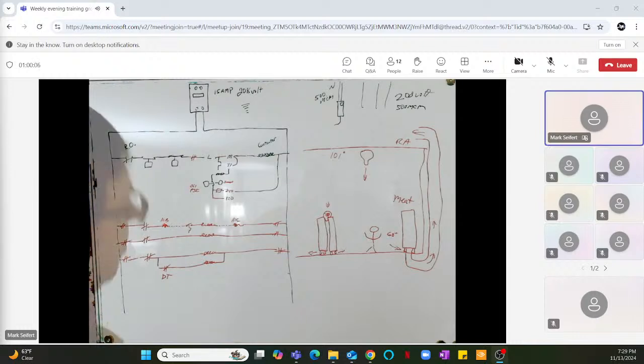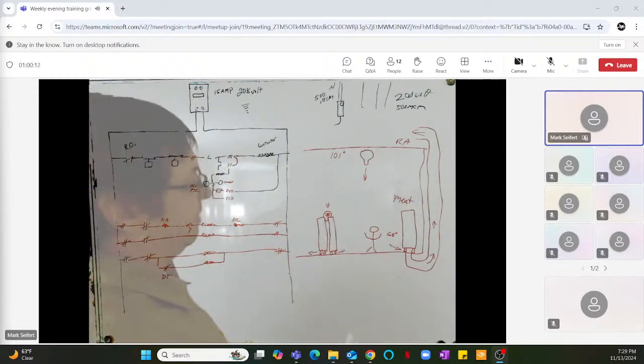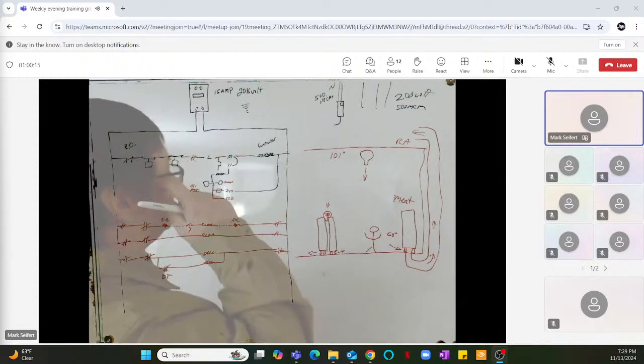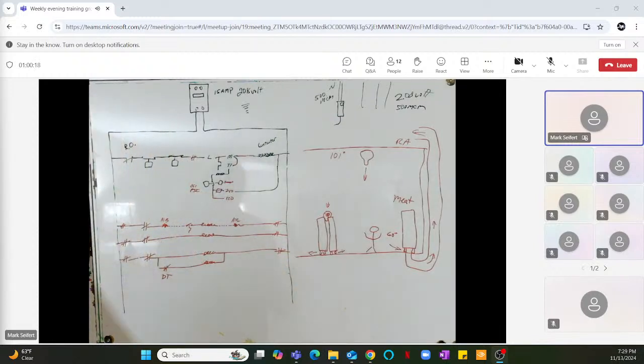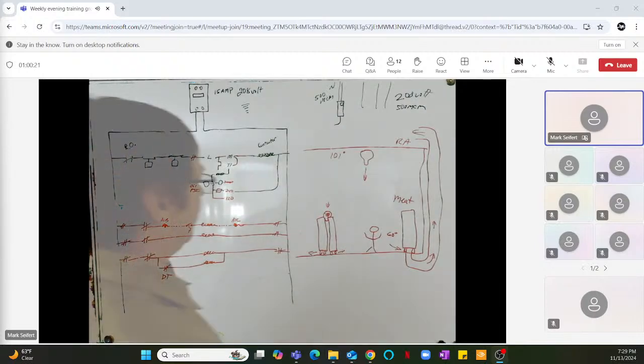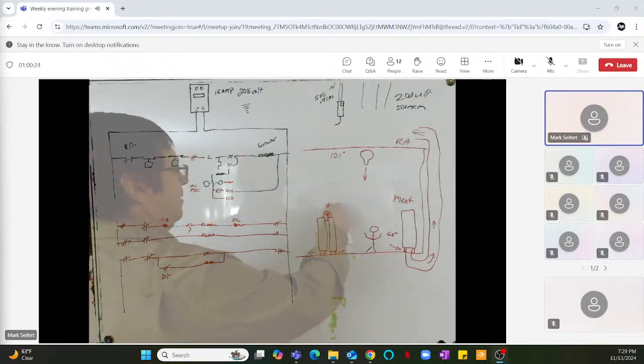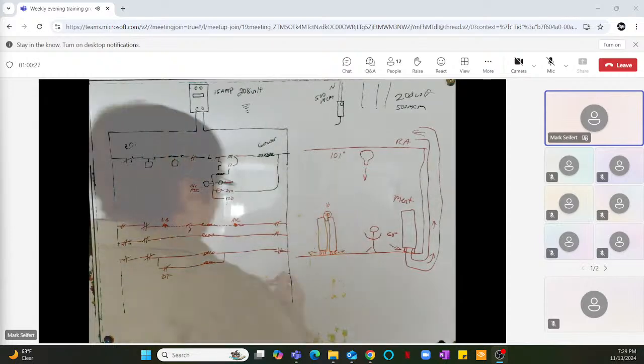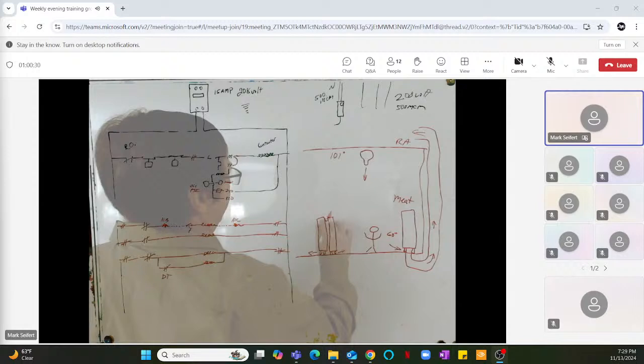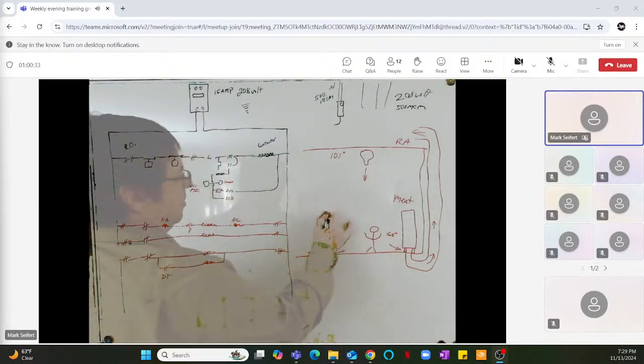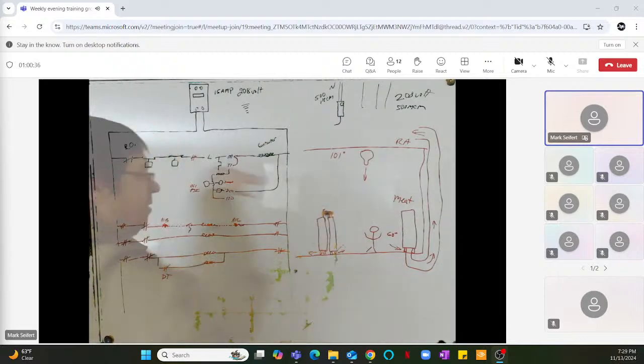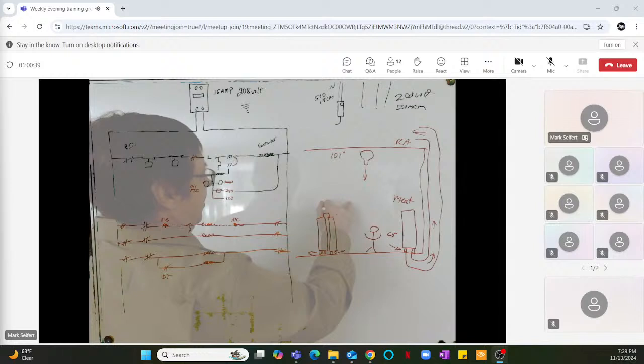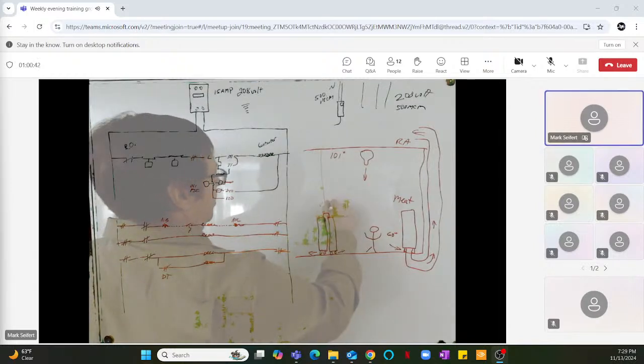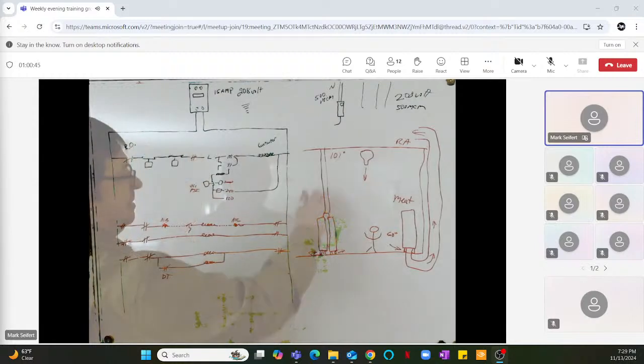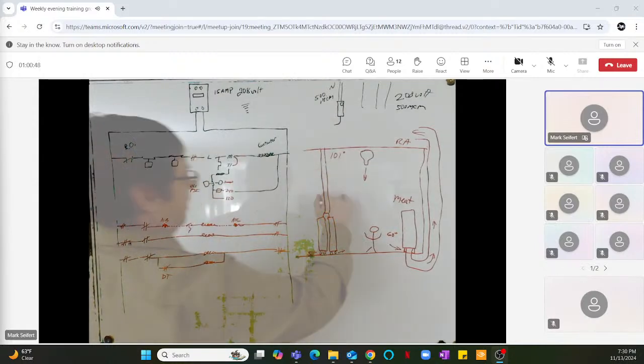If you've got a particularly bad store, like we had at an Albertsons, a small store with no undercase returns, it was a disaster. I mean, if you're at your wit's end, the air handler's working, everybody's screaming, the store's warm, tears are coming, nobody can fix it, there is a way. You could go out to your frozen food cases, put an adapter here all the way across the case, and put in a return air. It looks like a false column. Seal off the top of the cases. Now all of a sudden you've got a false column that's moving a bunch of air up.